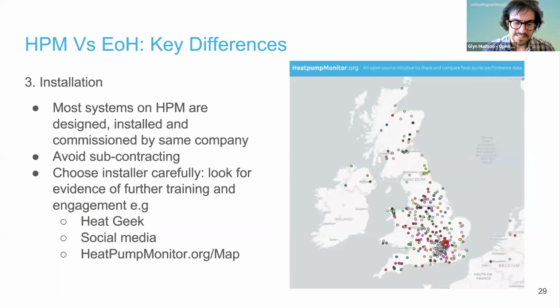And just to touch on the installation of the heat pumps, most of the systems on HeatPumpMonitor were designed and installed and commissioned by the same company. Each individual heat pump was installed by the same company. You don't have a different company doing the design, a different company doing the installation, and maybe someone else doing the commissioning. That's definitely not the way to get good heat pump performance.